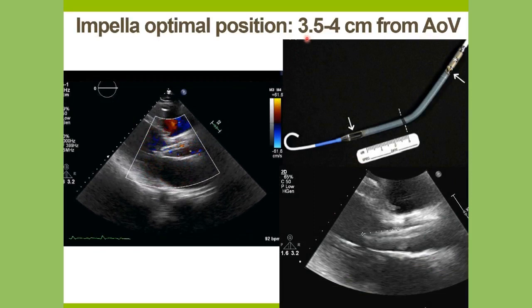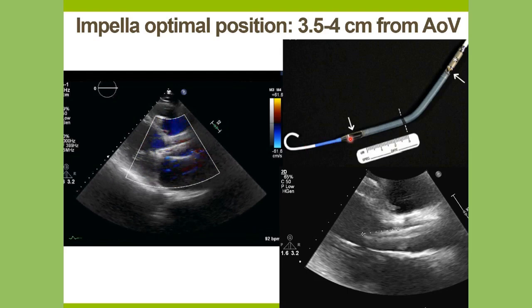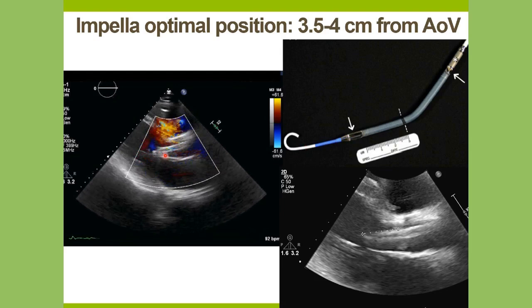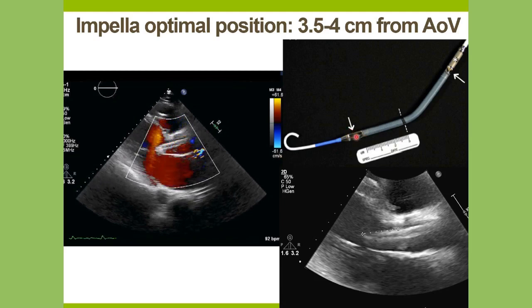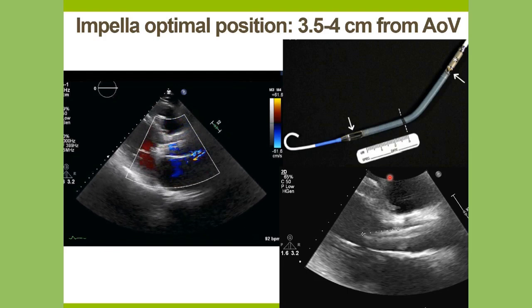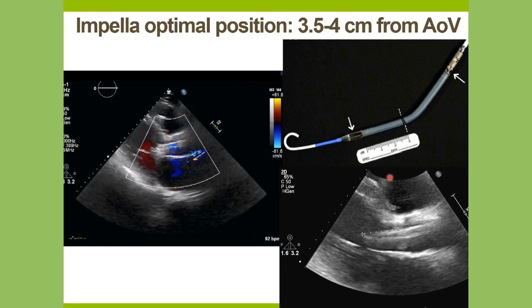We repositioned the Impella. The optimal position is 3.5 to 4 centimeters from the aortic valve. Sometimes the echogenic tip is not very clear, so application of color Doppler can help show blood flow at the inlet and serve as a guide for measurement. After torque and advancement, we were able to achieve 3.5 liters of support with no problem.